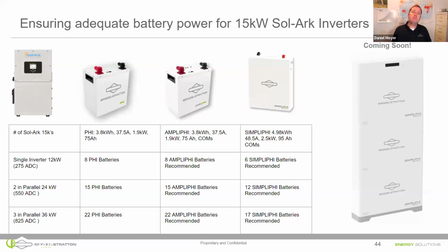Nathan, can you talk a little about how the 6.6 is positioned to be a perfect match for power output with that Sol-Ark 15K? The unique factor about the 6.6 shown there is that it's coming soon. The number of batteries required to run this Sol-Ark 15K is based on needing the full capacity of that inverter, being able to provide 12 kilowatts straight from the batteries in a grid-down situation. That stack of 3 batteries on the right side of your screen can do that, since these batteries can discharge at 1C when required. So what you're looking at is a stack of three, each one 6.6 kilowatt hours, with a power distribution unit and communications hub at the top.